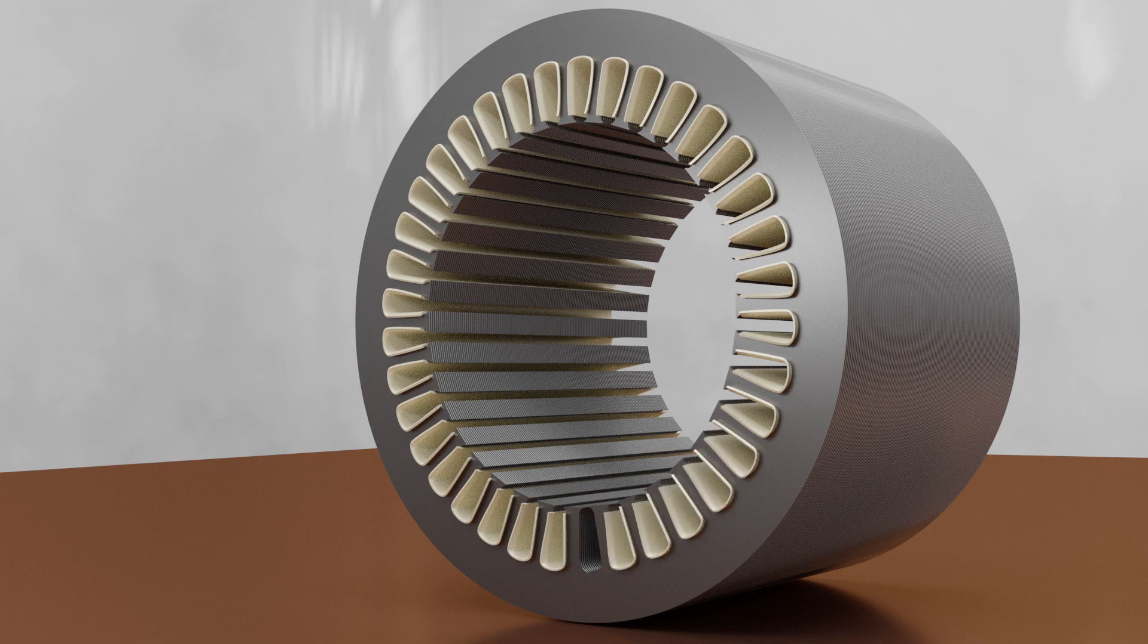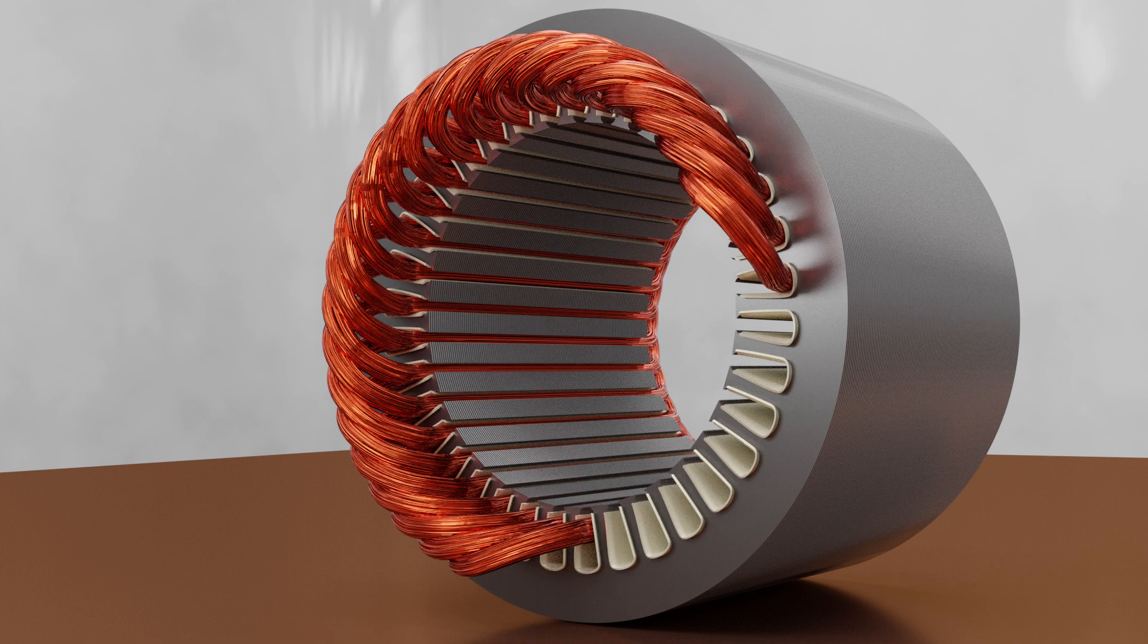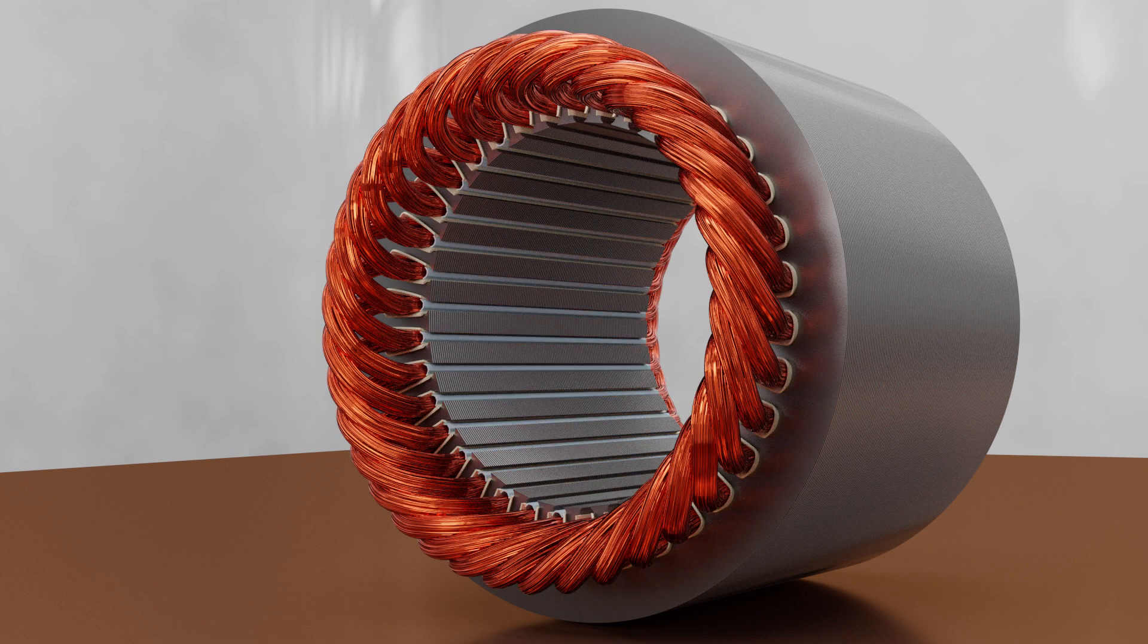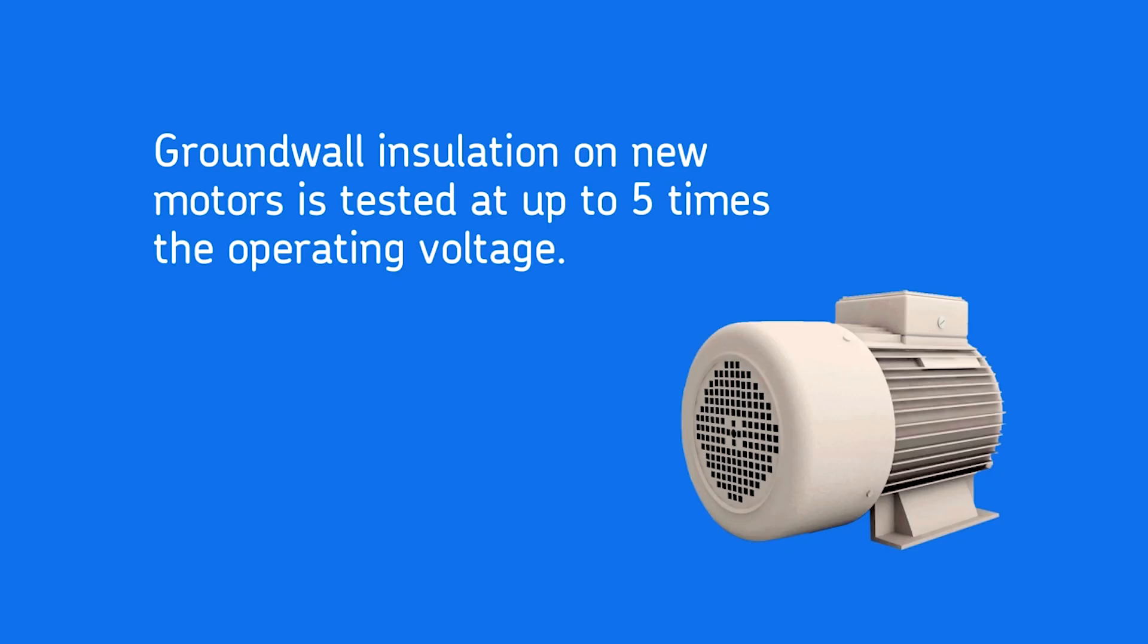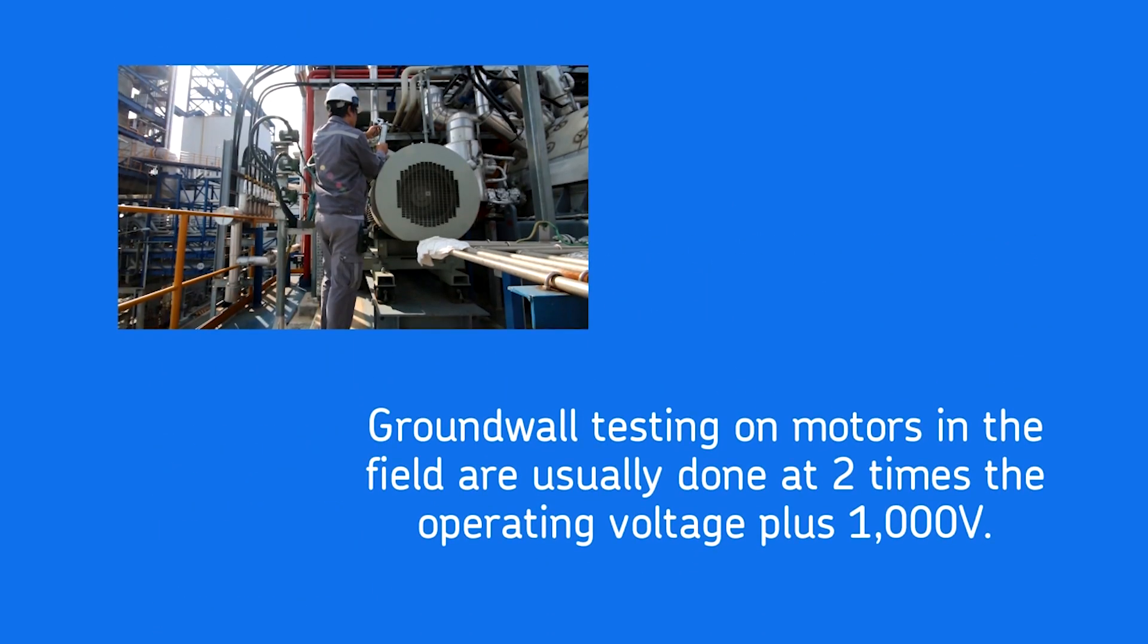The ground-wall insulation is the insulation between the stator windings and the stator core. When the motor is new, this ground-wall insulation is tested at voltages up to five times the operating voltage. For motors in the field, ground-wall testing is usually done at two times operating voltage plus one thousand volts.